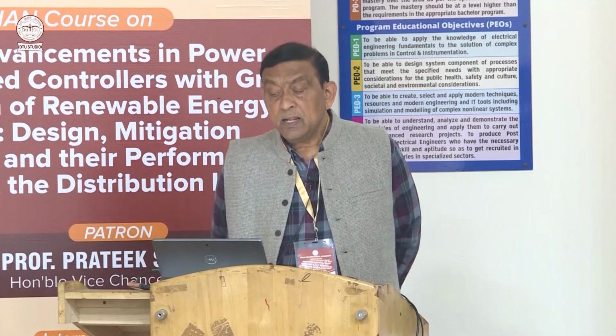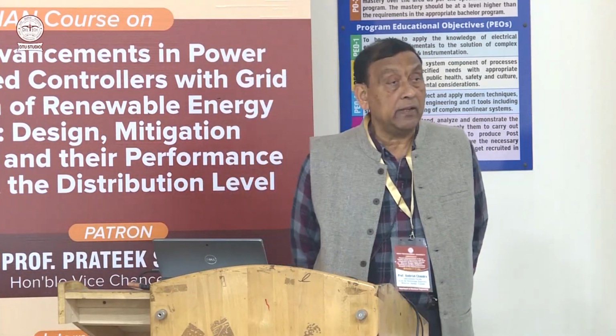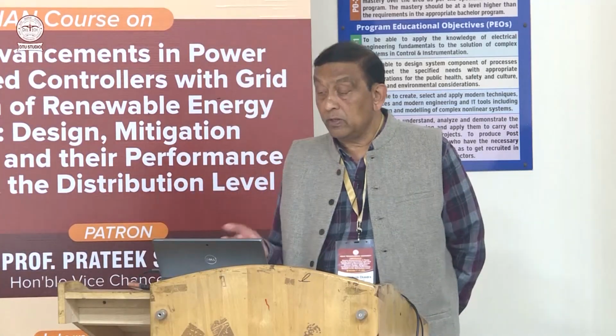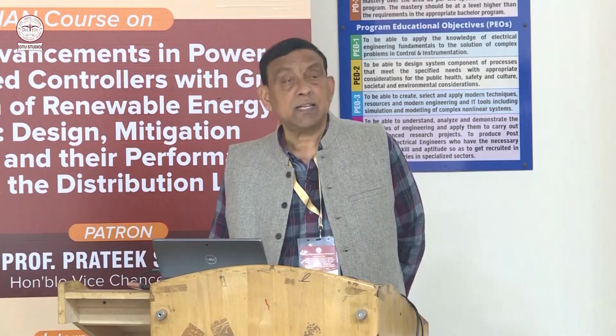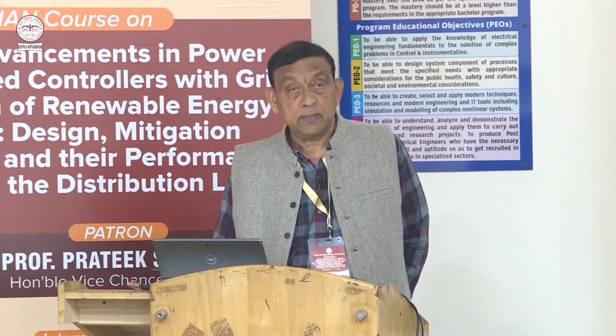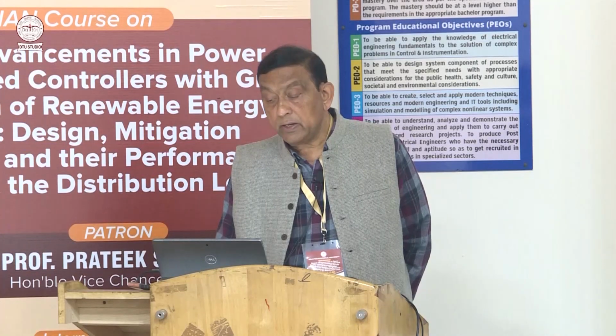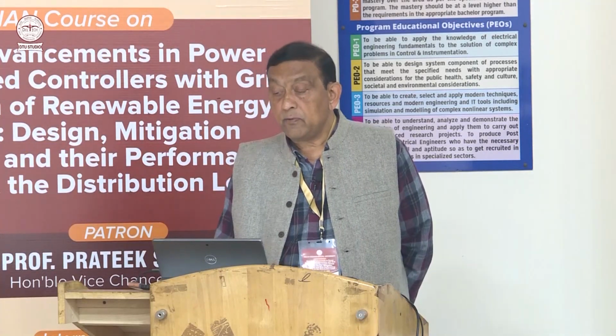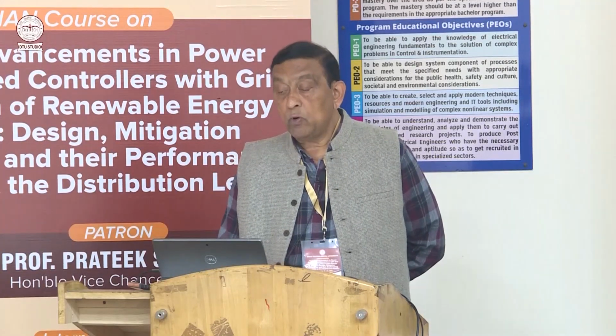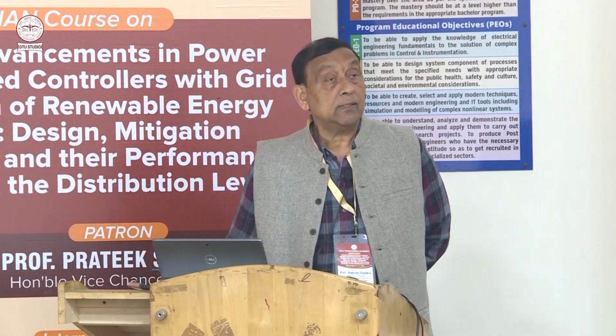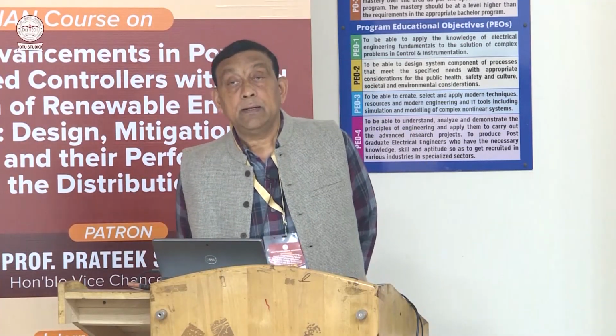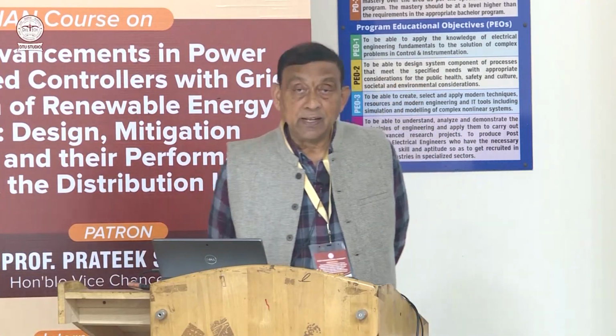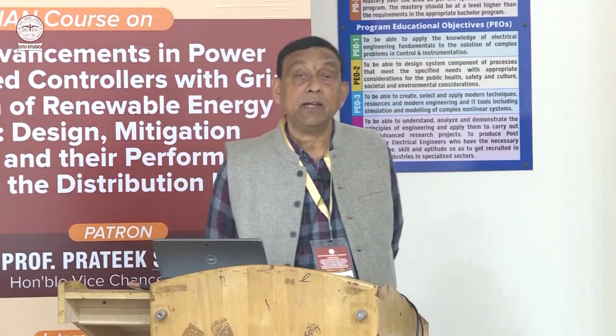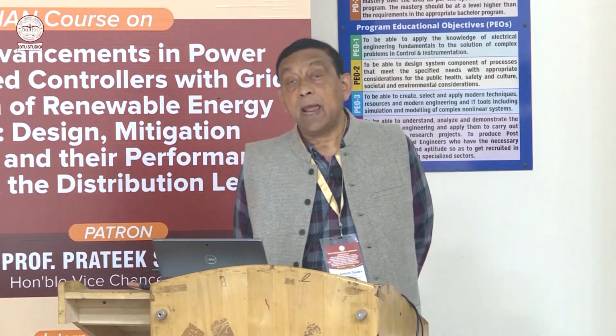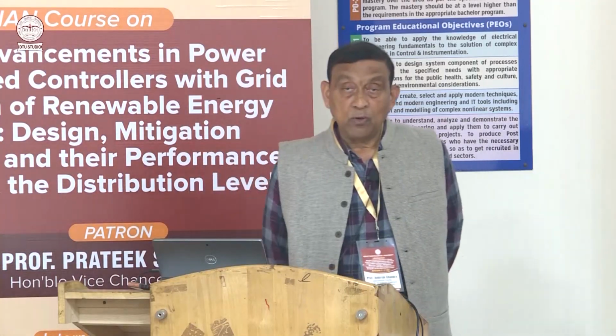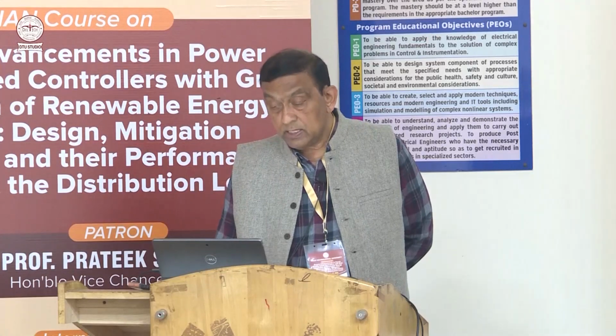Then we're talking about the standard 519. Initially it was 1992, but it has been updated in 2014 and 2022, and they have changed a little bit. So there are some minor changes, but for us they are not any major change. Then we were talking about interharmonics, same type of problem, and then we were talking about the notching, the drop of voltage during commutation of current, because there is a source inductance which will prevent the current from reducing to 0 instantaneously, so it will take some time because of inductance, and in another set of thyristors it will take some time to build up the current, so there is a commutation overlap, and because of that we have the voltage drop.